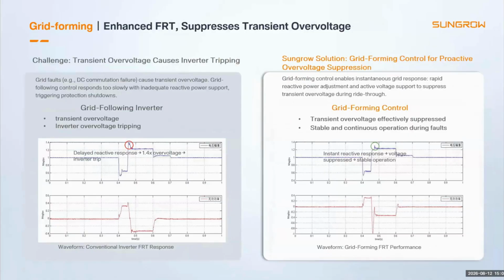Grid faults can also cause transient overvoltage. If the inverter responds too slowly, protection may operate and disconnect the unit. With grid forming control, the inverter rapidly adjusts the reactive power and actively supports the voltage. This helps suppress transient overvoltage and keep the inverter connected through the fault. For weak grids and demanding grid codes, this significantly improves fault ride-through capability.